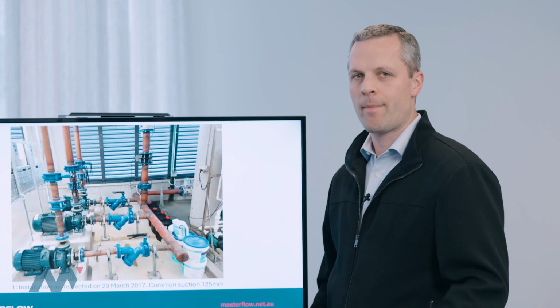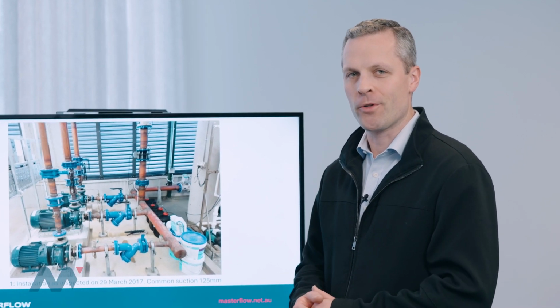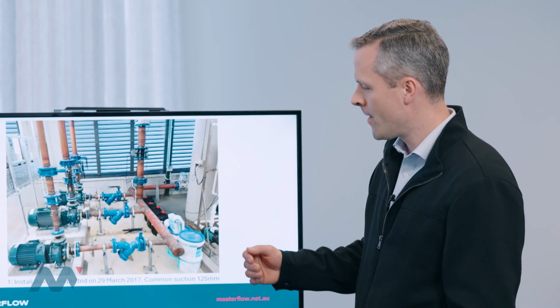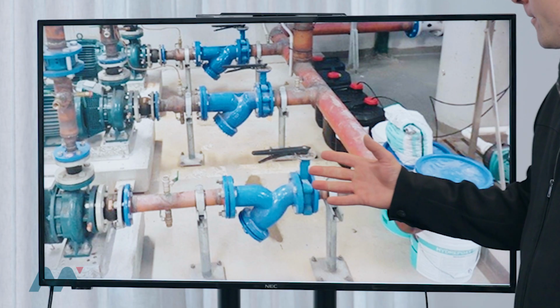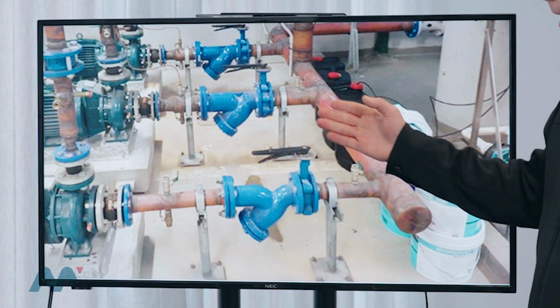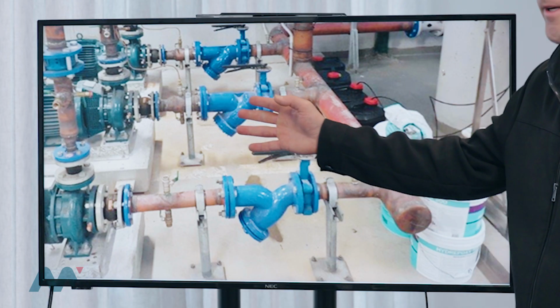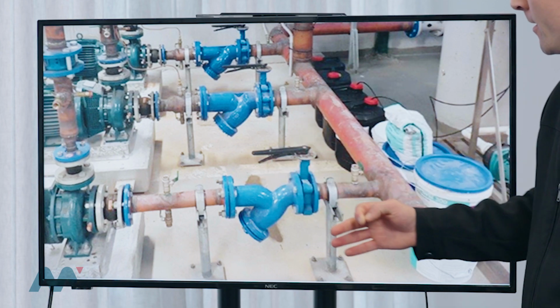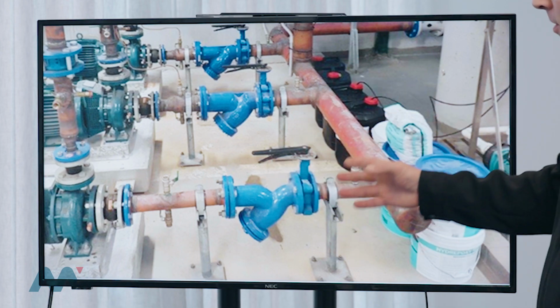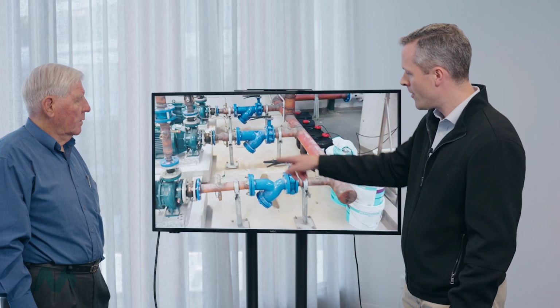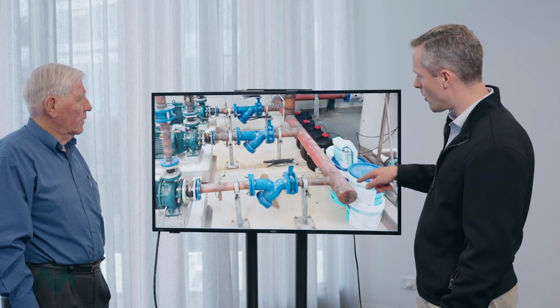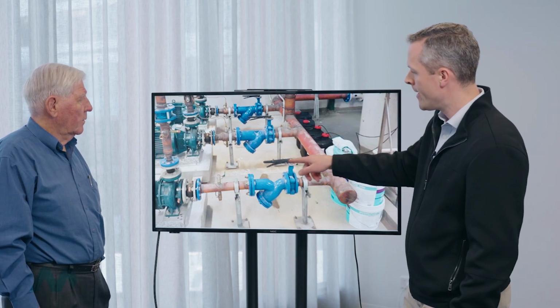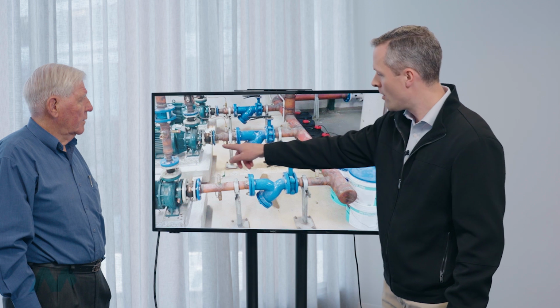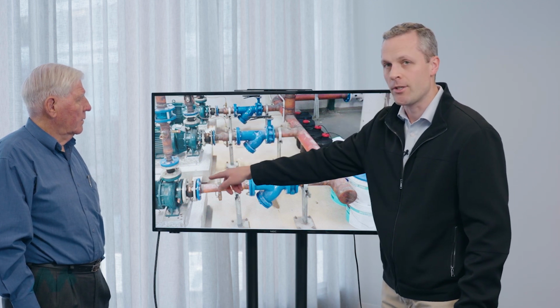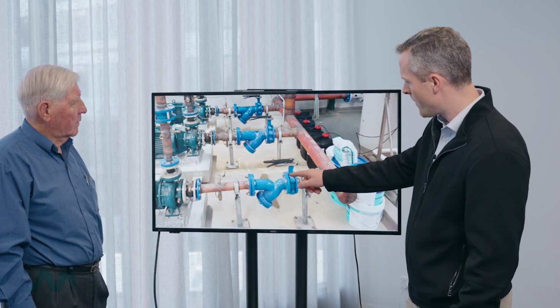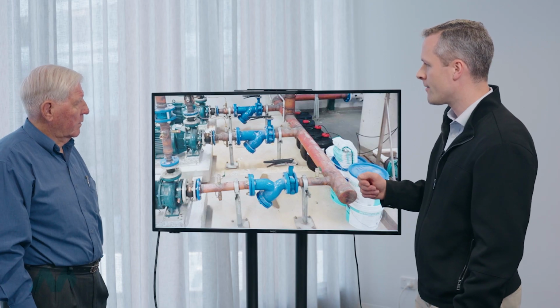It's that simple. So back to the noise that was first reported about this installation. There's a couple of things we're going to look at here. Firstly, we're going to look at pipe sizing and the general plumbing here, and then we're going to talk about the pump sizing. So let's have a talk about the pipe sizing. The branch from each pump was 80mm, going into a 125mm header. The pump suction was 80mm at each pump. So what do you see here, Keith?